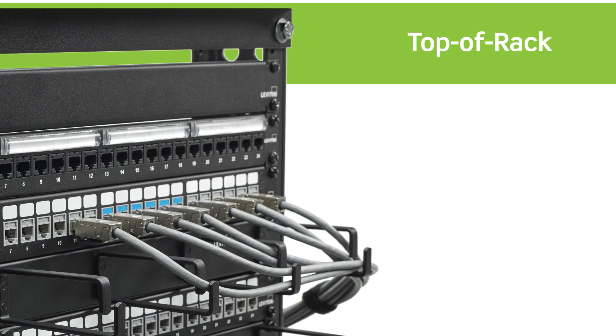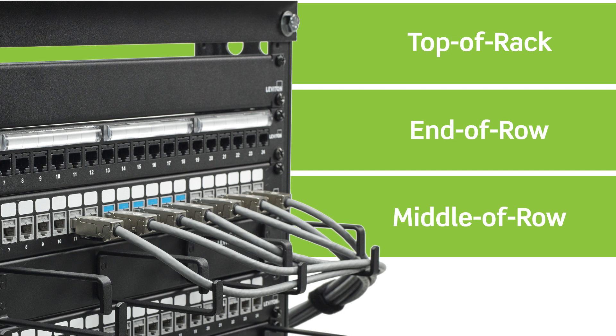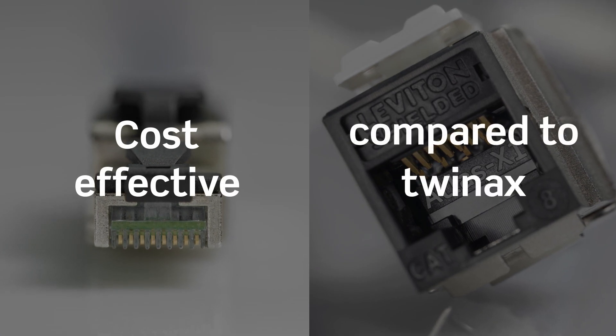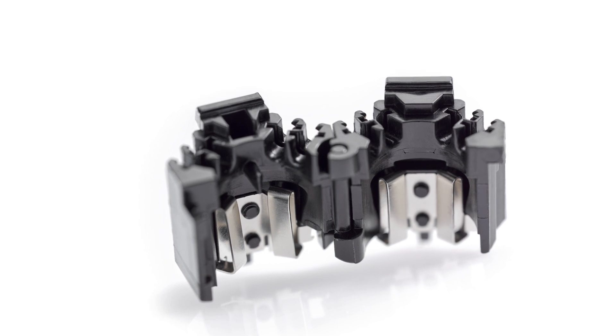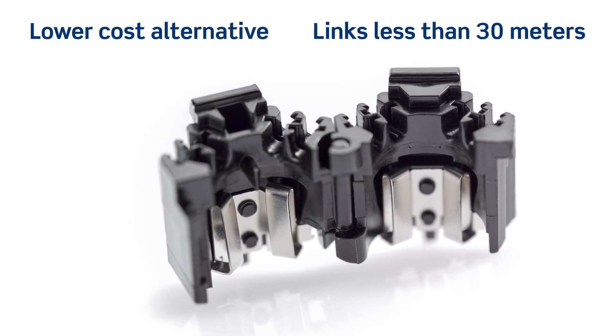This makes CAT 8 a versatile solution for most top-of-rack, end-of-row, and middle-of-row topologies. CAT 8 also provides a lower-cost alternative to twin-axial cable and is backwards compatible, unlike twinax. CAT 8 is also a lower-cost alternative to multi-mode fiber cable in lengths less than 30 meters.